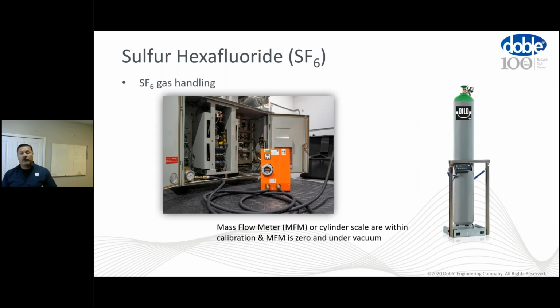Having a flow meter or cylinder scale that are calibrated, and also, by the way, if you're using a mass flow meter, that it doesn't have gas from a prior recovery job or anything like that, so we can avoid contamination. You want to start with that mass flow meter at 0. Your scale, you want to be sure that it's calibrated and it's designed to handle cylinders. But we don't want to see a scale that you buy at Bed Bath & Beyond or Walmart or some other store that is not going to be able to handle what the industriousness of a cylinder is.